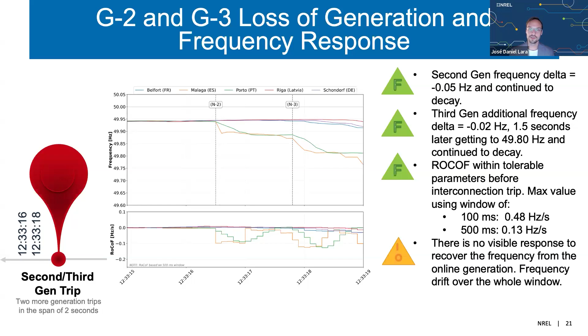In the second phase of the event, you can see here the loss of the N-2 and N-3 that happen very close to each other. Again, the frequency delta, the rate of change of frequencies, is higher than the previous window, but it's still not large enough to trigger rate of change of frequency protections. Right? Again, there's no visible response so far, after this happened, of the system trying to recover the frequency. So again, the deltas here for frequency don't really explain why there could be a lack of response to try to bring the system back from the active power perspective and the frequency.